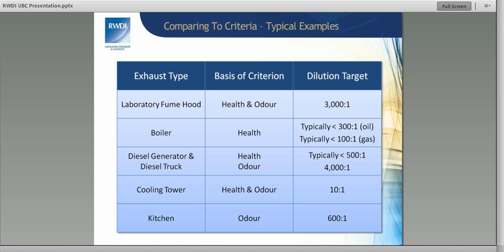The problem is the volume of exhaust these cooling towers produce is enormous, on the order of hundreds of thousands of cubic feet per minute. That's a lot - a typical laboratory fume hood exhaust produces between 1,000 and 20,000 cubic feet per minute, not 300,000 or 400,000. When you have that much volume, it's very hard for the environment to disperse it. So let's say we're talking about a dilution ratio of 2 to 1.